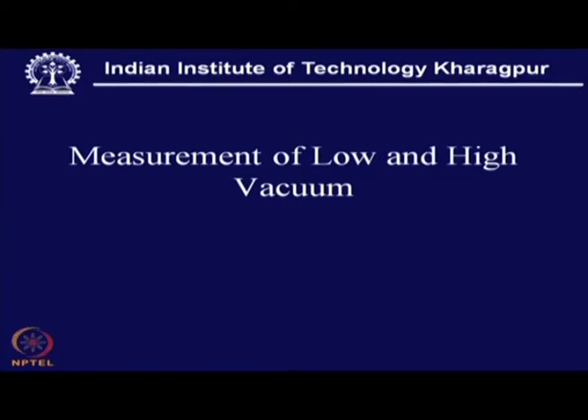Now here it is important to know how to have a full assessment of this process, that means measurement of the low pressure, that means evacuation of the system, how effective the pumping system is and how quickly it can pump down to that low pressure. For that we need some sensing element to measure that low pressure. And also during the deposition, when the pressure is relatively high, that monitoring is also necessary.